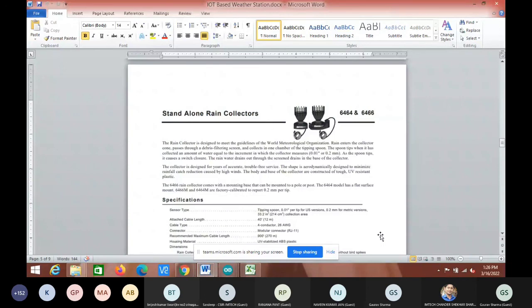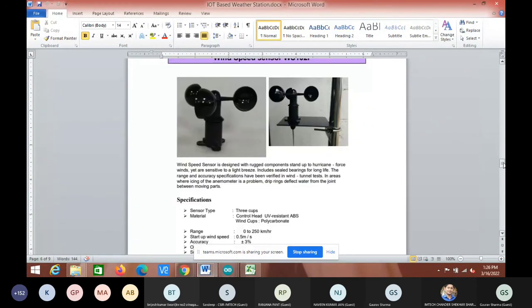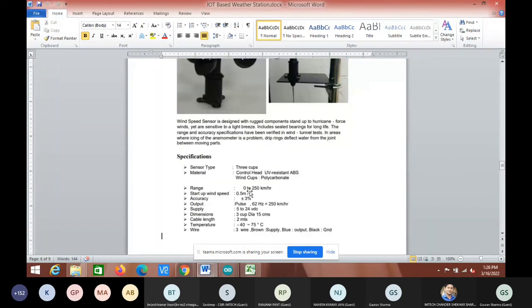In this sensor you can see, this is the wind speed sensor. It tells us the range, between 0 to 250 kilometers per hour speed, with an accuracy of plus minus 3%, and the output is 62 hertz equals 250 kilometers per hour. If I put a DSO, digital storage oscilloscope, at the output terminal of the sensor, there will be a pulse output. If it's 62 hertz pulse output, it's rotating at 250 kilometers per hour, and if it's not rotating, it will show 0, so at 0 hertz there's 0 kilometers per hour. By using these values, I will make a calibration formula.